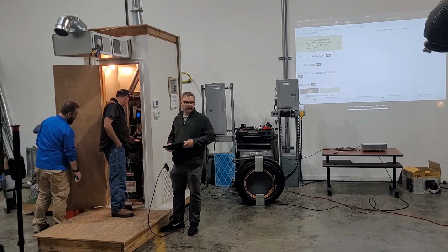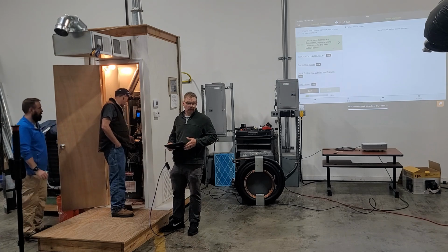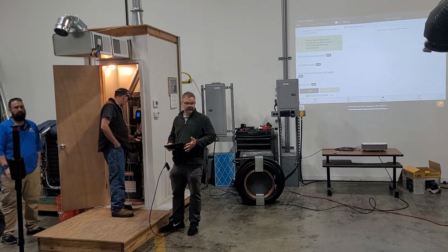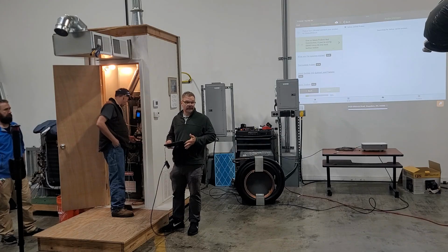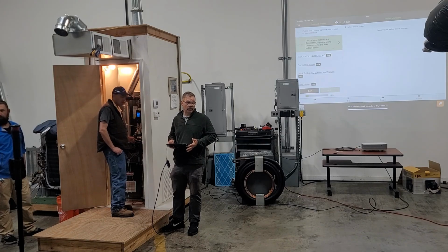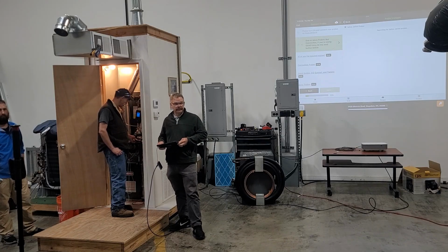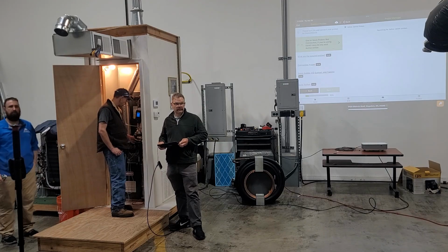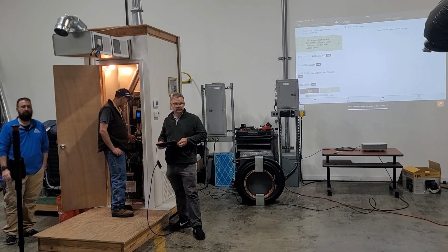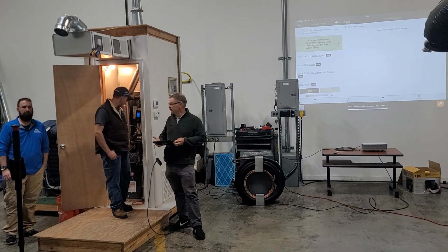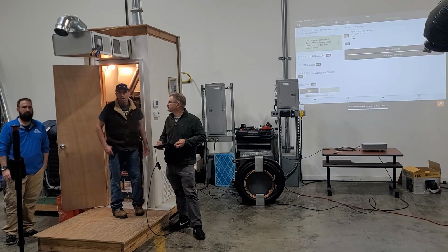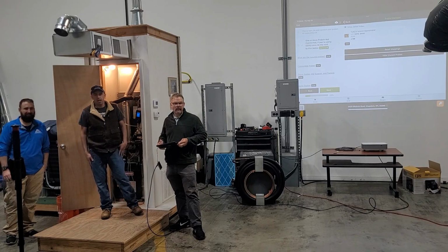Any compatible dual port manometer is recommended, so take our static pressure that way we don't have to switch probes. I use the dual port because it's a visual difference between that and my gas pressure gauges. That's to make it idiot proof. And Jimmy's saying the same. I'm a pretty big idiot, so that just helps.